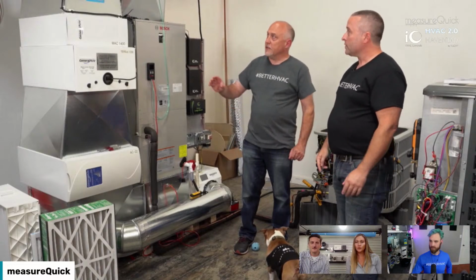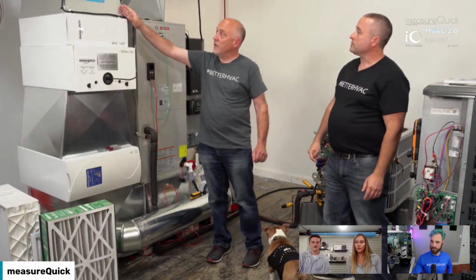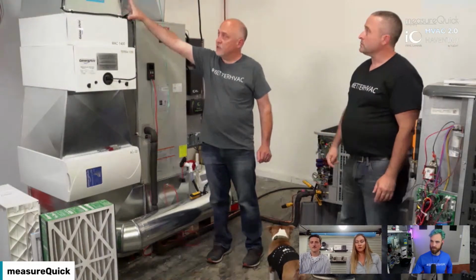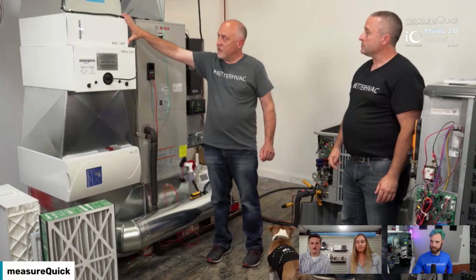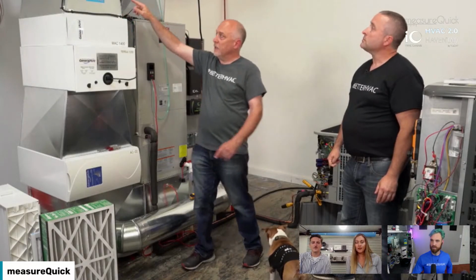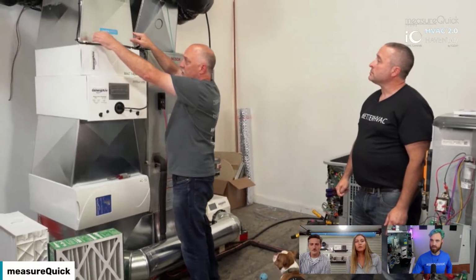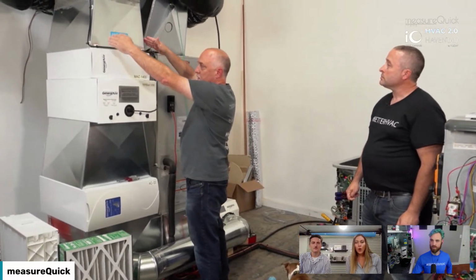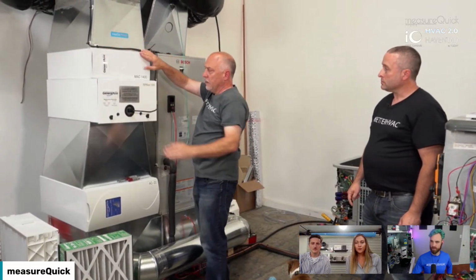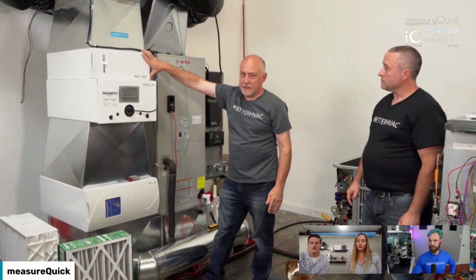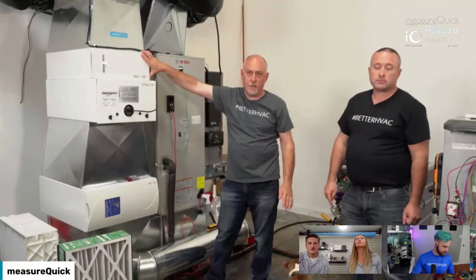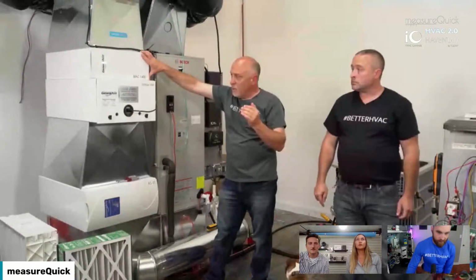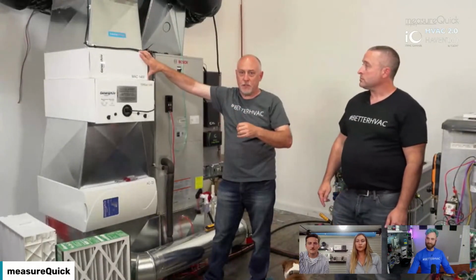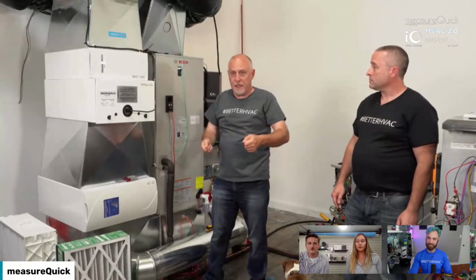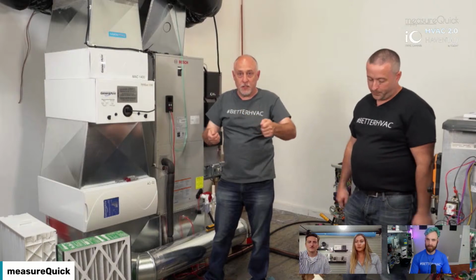The other thing that's interesting to talk about regarding the installation is the big drop into each one of these air cleaners. There are some important things when you're designing duct systems - you want to make sure your transitions allow the air time to move out across the full media. We want to keep the air velocity somewhere between 250 and 300 feet per minute, ideally. If you get the air moving too fast through here, what happens is you get what's called sifting - like when you're a kid with a sifter filled with sand, it really doesn't go anywhere until you start to move it.